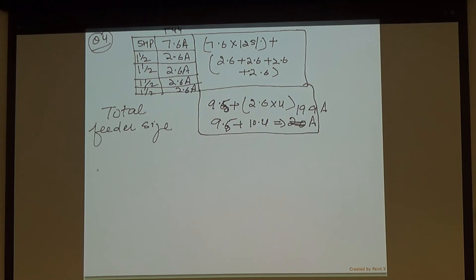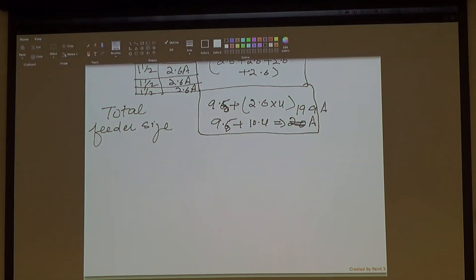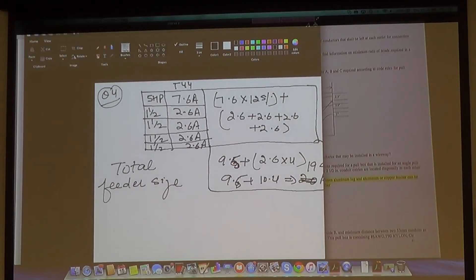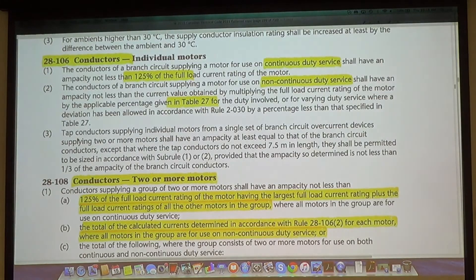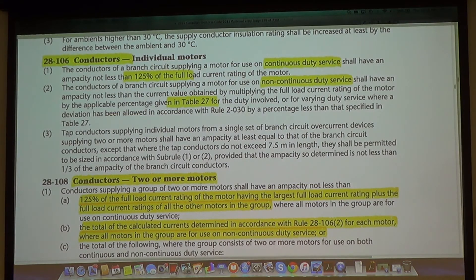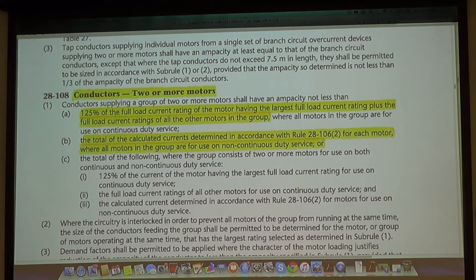So the second thing I'm going to teach you, so 28.108, if you go back to the rule, I'll put this on the screen one more time, but let's go highlight the stuff first. So here, for a continuous duty cycle, you're going to go sub rule A and highlight 125% of your largest FLA plus the FLAs of all other motors. That's what we just followed.